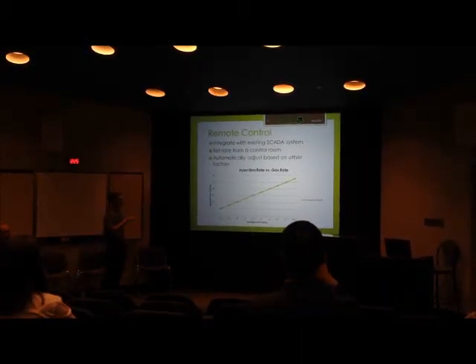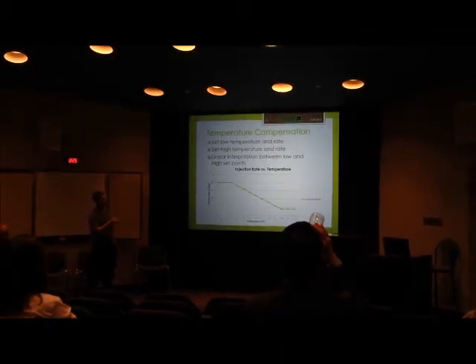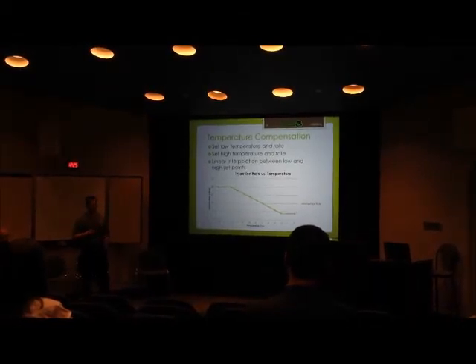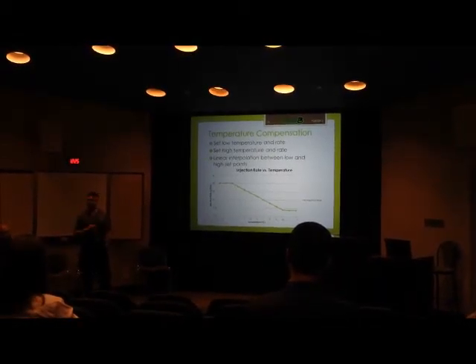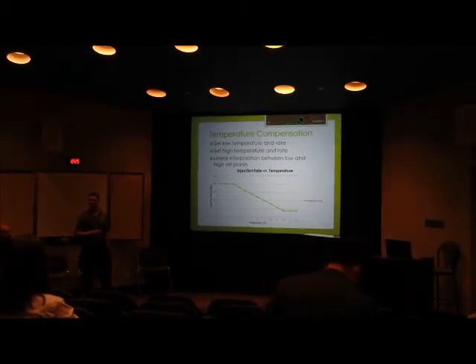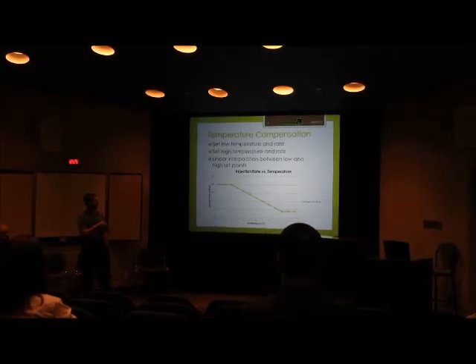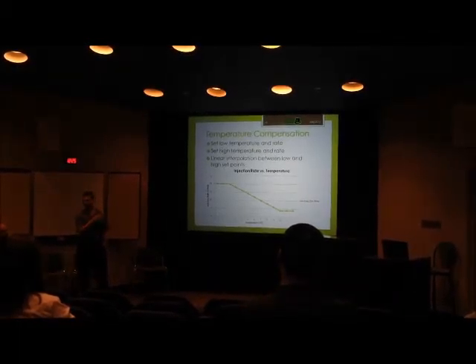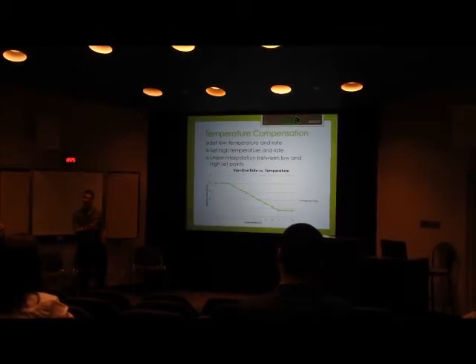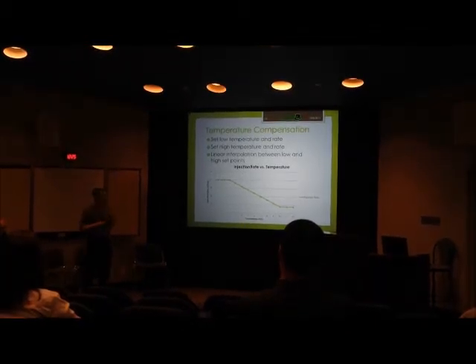If this was off the temperature, or sorry, I'll back up. This one off the temperature has really intrigued a lot of my customers. So they have their host at their compressor station, they have a thermowell coming in there, they already know their hydrate curve, say 4 degrees. Well, if that pipeline starts to get into that 4 degrees, how do you tell your pumps to kick up the methanol out in the field without sending an operator out there or running the pumps already at a higher rate so you don't get into that hydrate range?